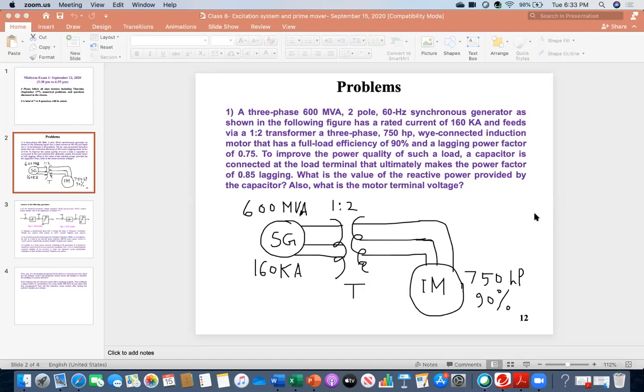The motor terminal voltage in this case is definitely the line voltage, line to line voltage, and not the phase voltage. Line to line voltage and RMS. I got 4.33 kV. Keep in mind the transformer has a turn ratio, left side and right side. So the motor terminal voltage will be 2 times larger than the primary side voltage. Dr. Ali, I got 4.33 kV, that's the line voltage, right? Yeah.